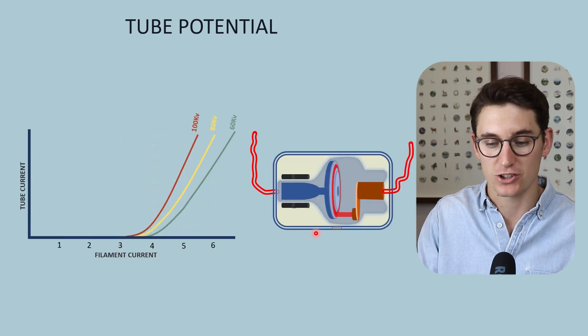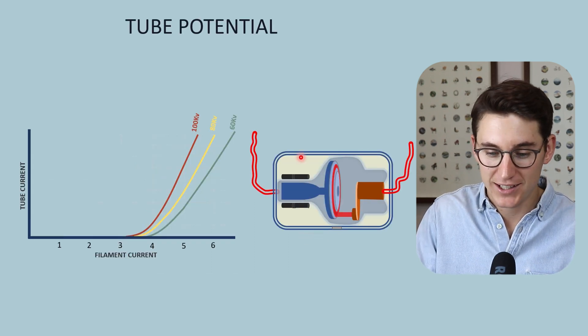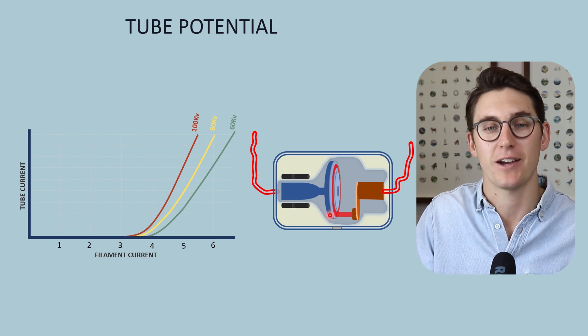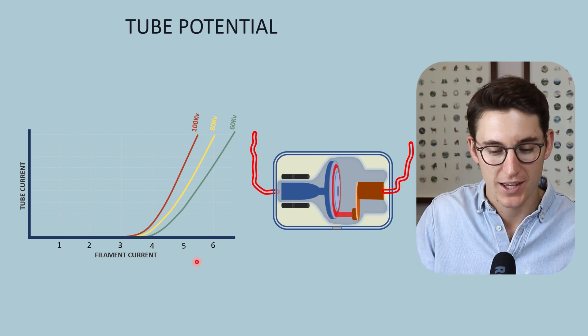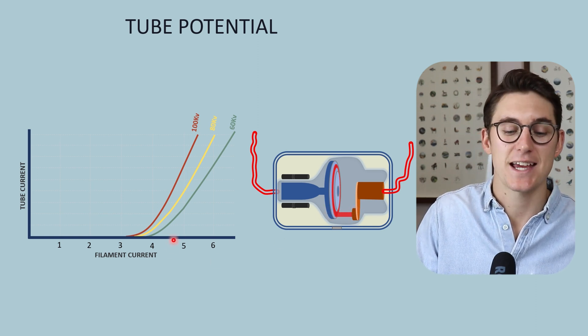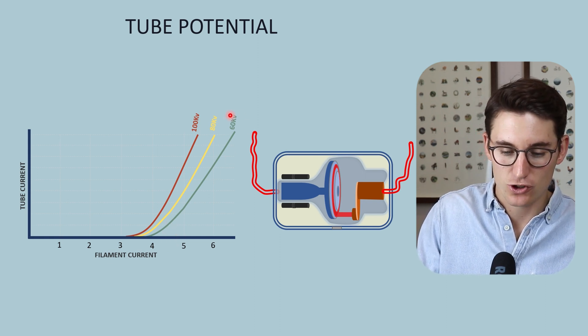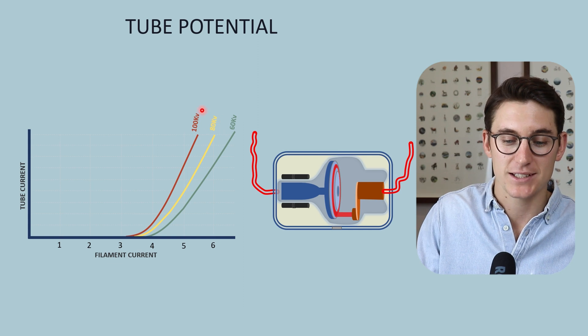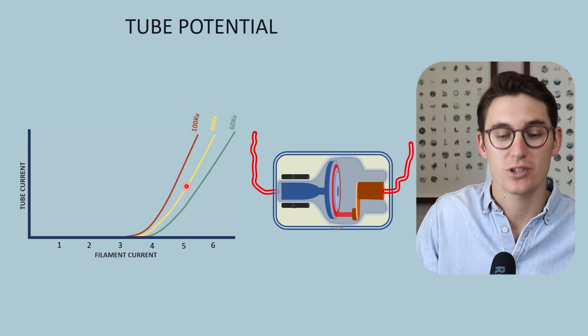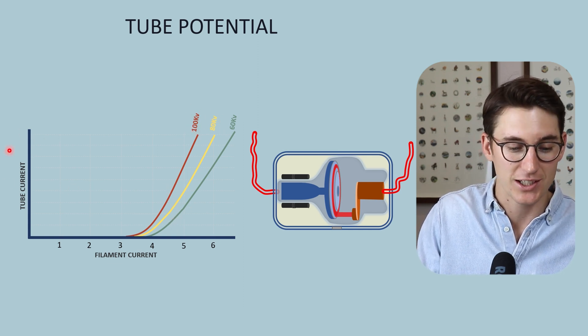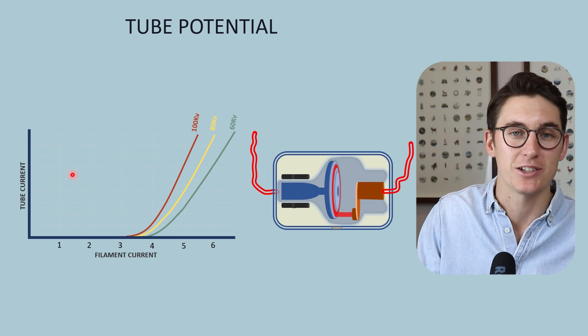Let's take an example. Here is our x-ray tube — we are running a potential difference between our cathode and our anode. At a set filament current, let's say four and a half, we can see that a tube potential of 60 versus 80 versus 100 kilovolts results in a marked difference in tube current, the number of electrons flowing across this space.